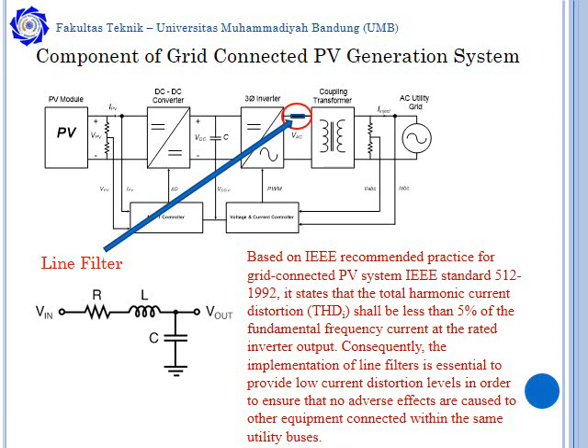The other component is the line filter. Based on IEEE recommended practice number 512, 1992, it states that the total harmonic current distortion should be less than 5% of the fundamental frequency current at the rated output. Consequently, the implementation of line filters is essential to provide lower current distortion levels in order to ensure that no adverse effects are caused to other equipment connected within the same utility bus.